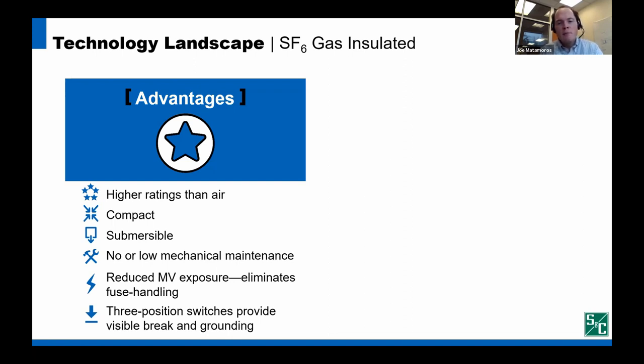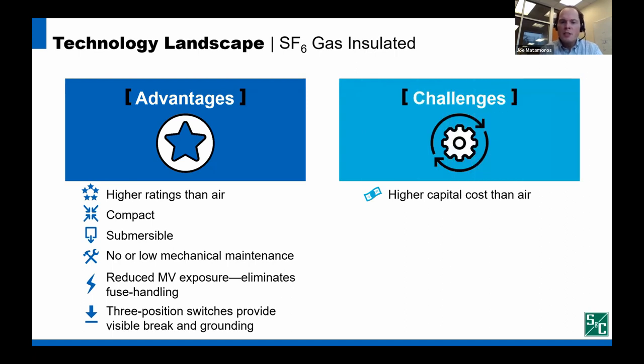Gas insulated gear has been implemented for decades. It is not applied as readily as air insulated gear due to several challenges. First challenge is that gas insulated gear has a higher capital cost than air insulated gear. It is typically not practical to serve all underground distribution switchgear, like underground residential distribution, with gas insulated gear. Instead, gas insulated distribution switchgear is typically employed selectively based on where the required ratings are needed, customer reliability requirements, and flooding susceptibility. The second challenge is SF6.